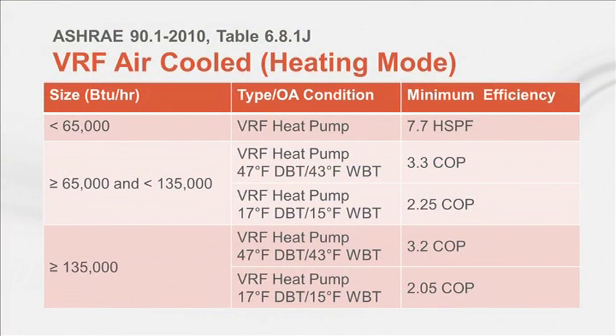And here's another excerpt from the table showing heating efficiencies. You can see that they are listed at two different operating conditions. Now, in the standard, the table also includes efficiency requirements for cooling-only units, water-cooled units, and equipment that uses either groundwater or a ground heat exchanger. Now, since we get questions on this often, let me pause a moment to explain some terms.